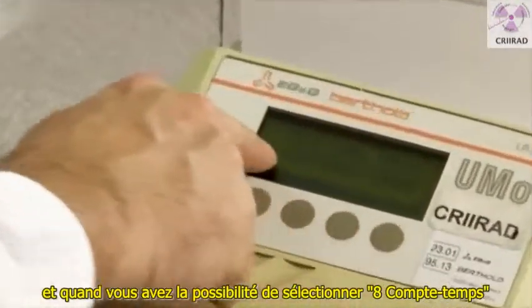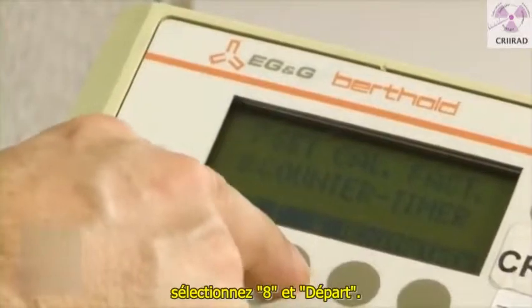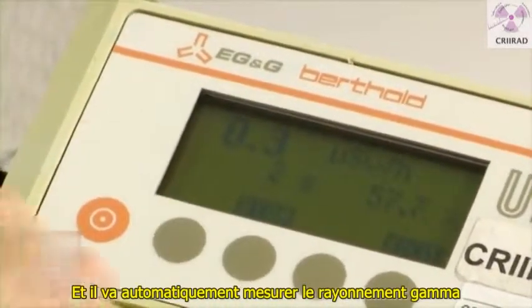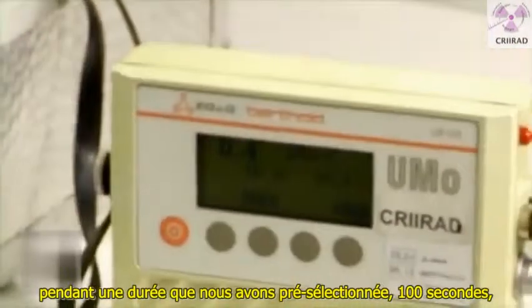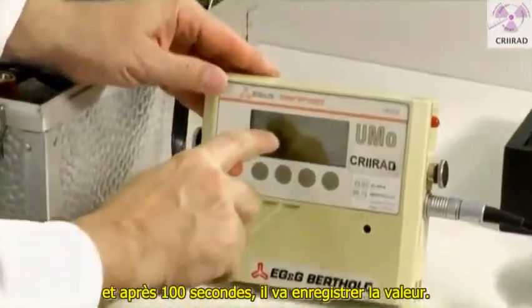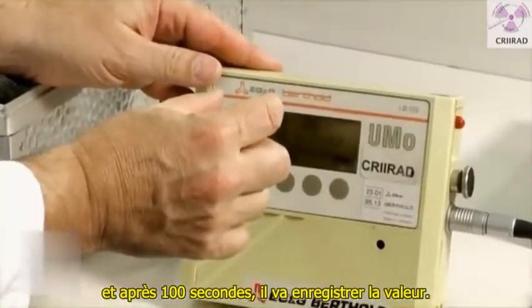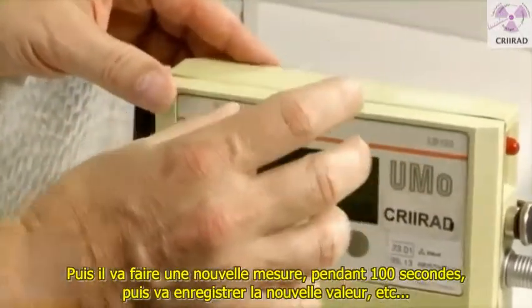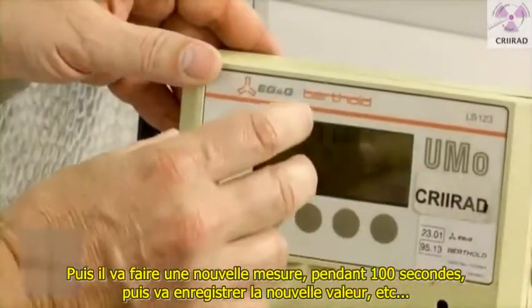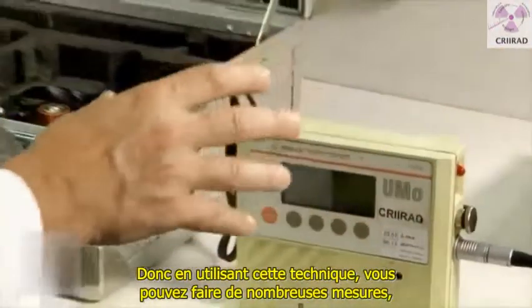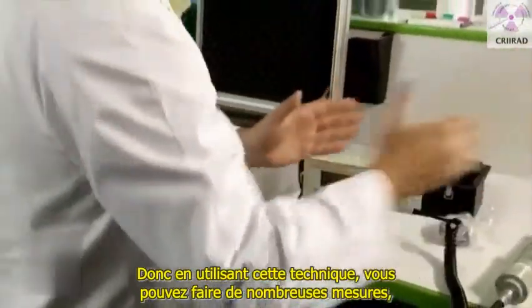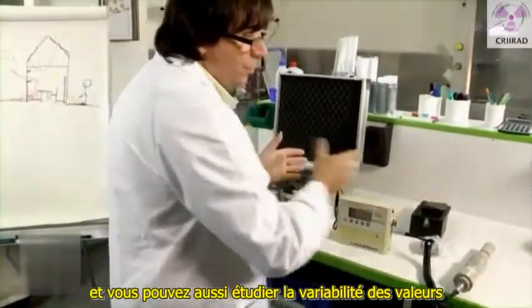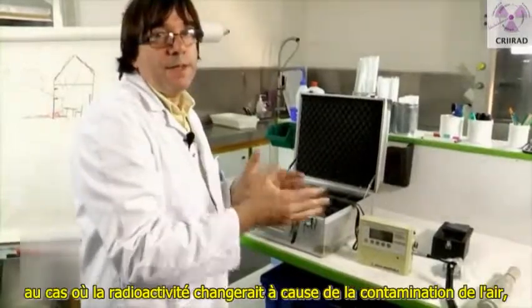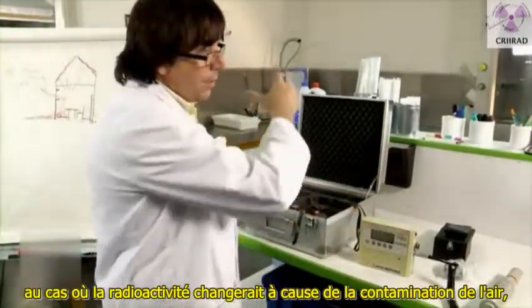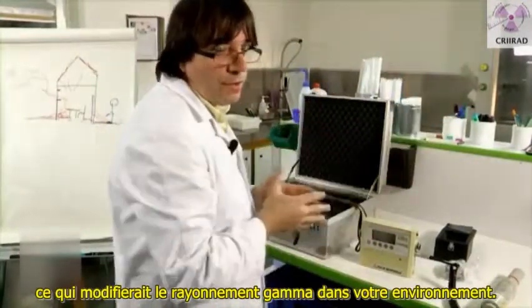and when you have the possibility to select 8 counter timer, you go to 8 and start. And it will automatically measure gamma radiation for a length of time that we pre-selected. It's 100 seconds. And after 100 seconds, it will make a record of the value. And then it will make a new measurement, 100 seconds, and make a record of the new value, etc. So, for example, using this technique, you can make many measurements, and you can also study the variability of the values during a certain period of time, in case the radiation may change because of contamination of the air that will change the gamma radiation in your environment.